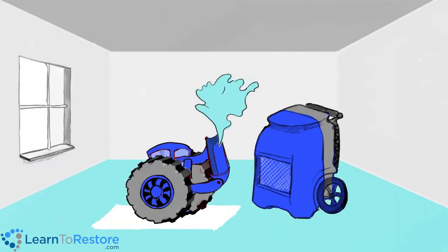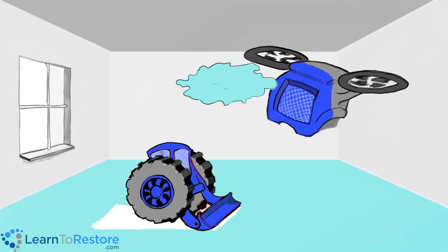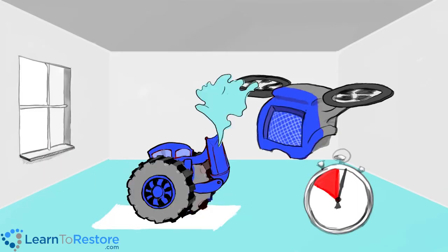The airmover's job is to bring energy to the materials, causing evaporation. This moves the water into the air as vapor. The job of the dehumidifier is to remove the water vapor from the air.